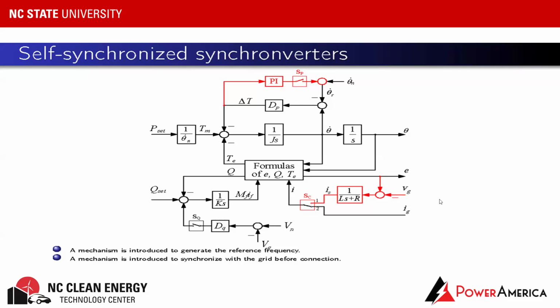Before we connect it to the grid, we are going to use the virtual current instead of the actual grid current for the VSM. And then that will allow us to achieve synchronization between the generated voltage and the grid voltage. In this way, we are able to connect the VSM to the grid without significant inrush current. So basically, we introduced two mechanisms. One is the PI controller, so that we are able to formulate the reference frequency theta R dot from the nominal frequency theta N dot, which is 60 Hertz in this country. In this way, we don't need to use a phase lock loop to extract the grid frequency.